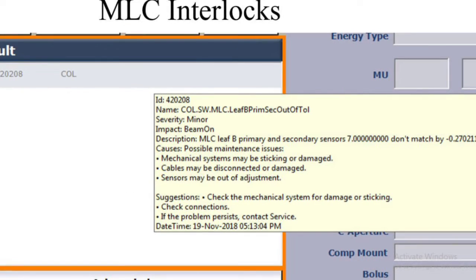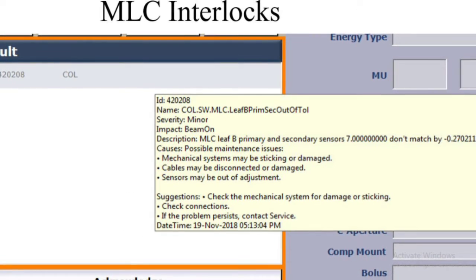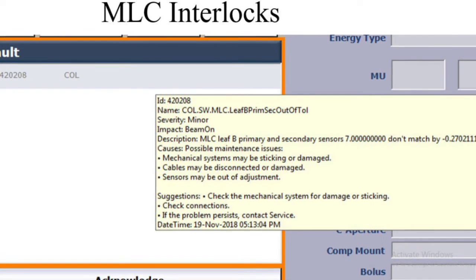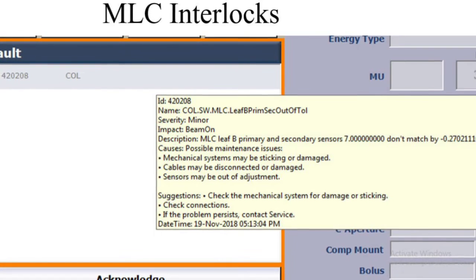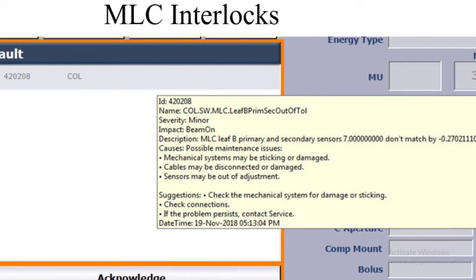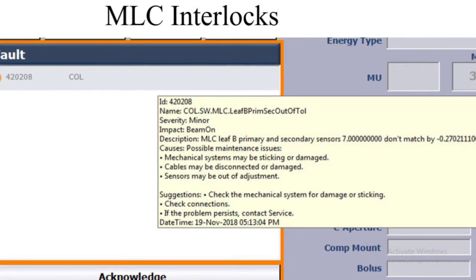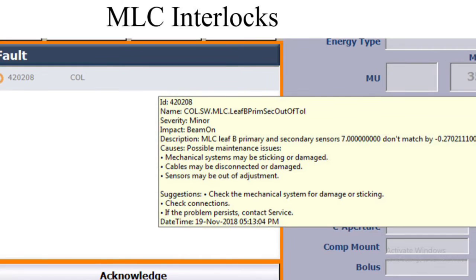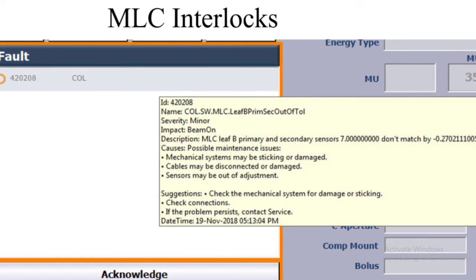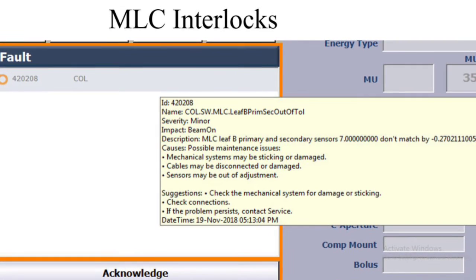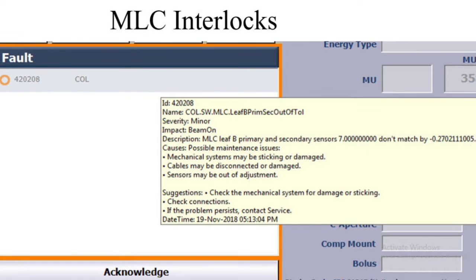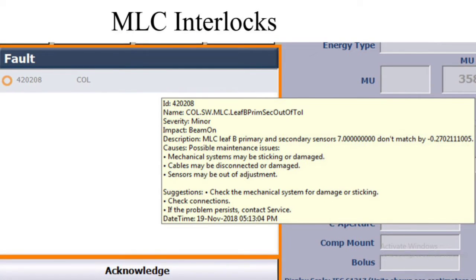Now let's move into the topic. Basically, whenever an interlock comes, TrueBeam will give plenty of information about the issue, like the interlock key, which gives information about the involved nodes and subnodes, interlock ID, interlock description, and a suggestion on how to clear that interlock. Here you can see the COL interlock in the treatment application, which is related to the MLC leaf. Now if we log into the service screen, we can see the MLC tab red in color.